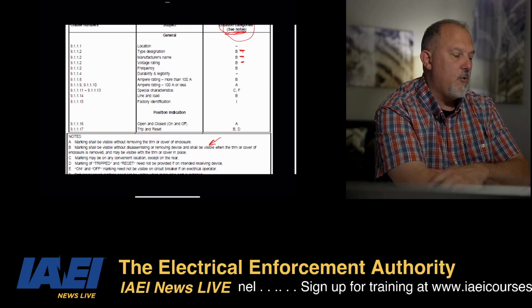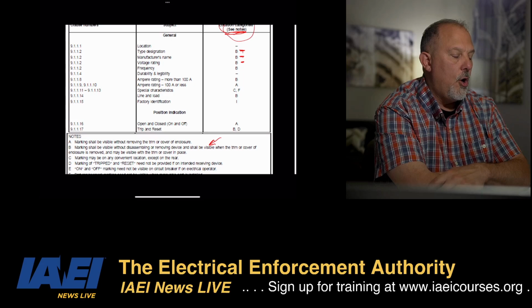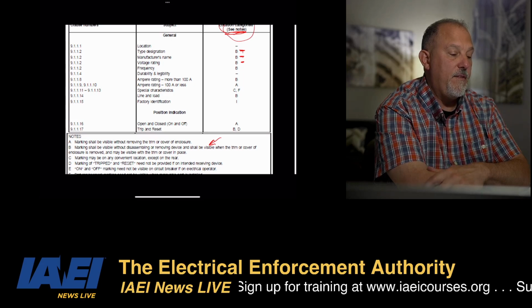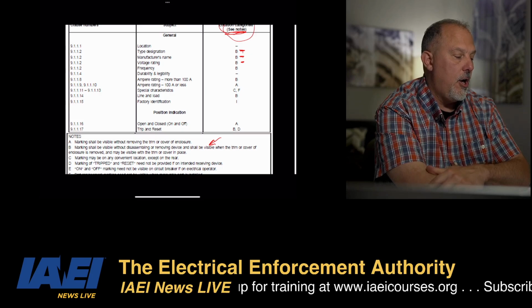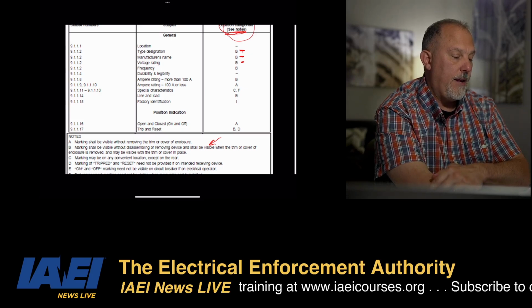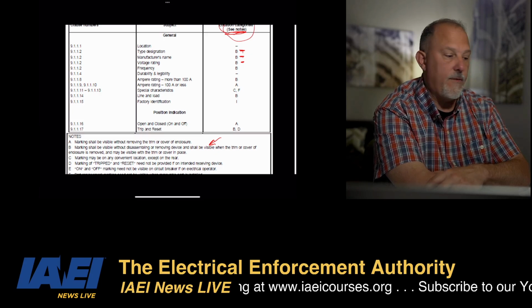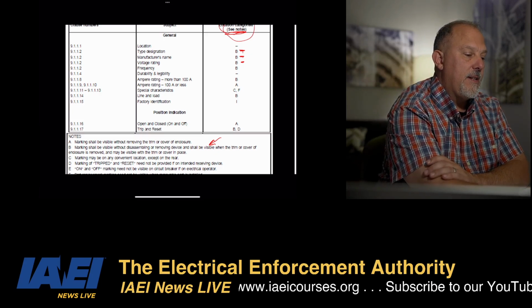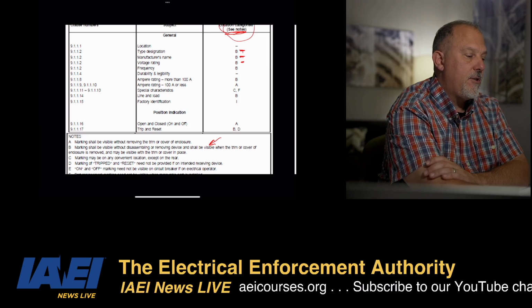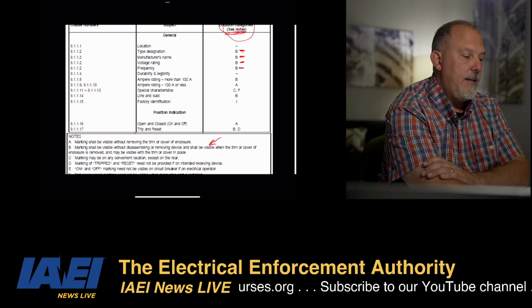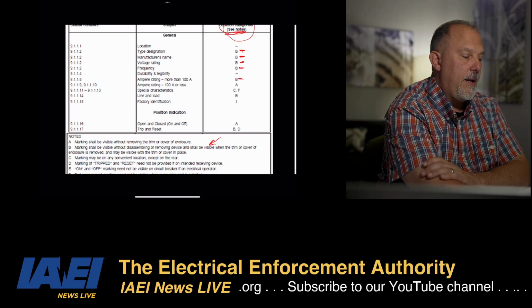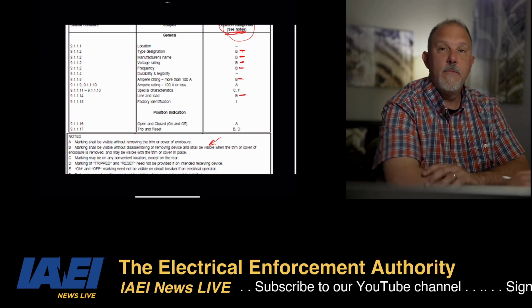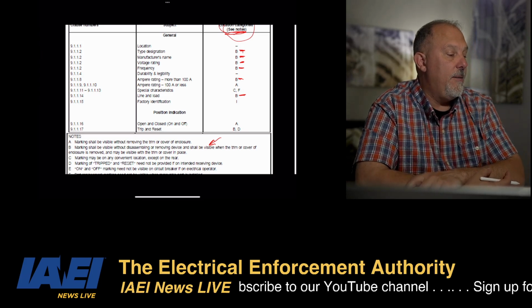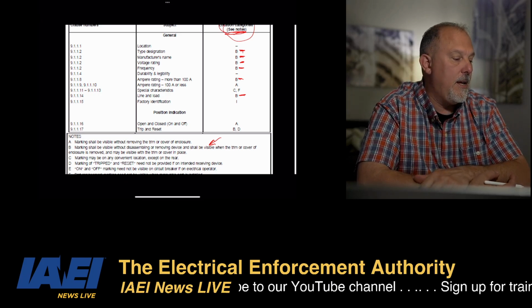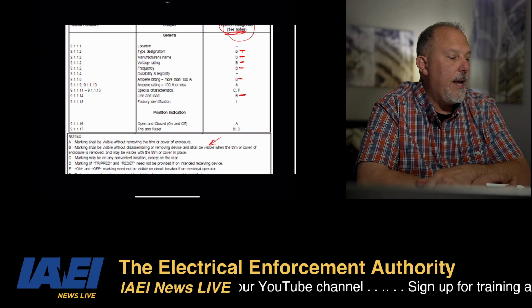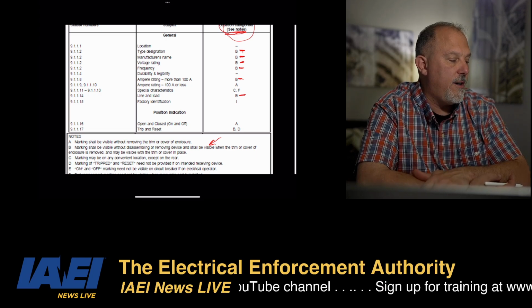Marking shall be visible without disassembling or removing the device, and shall be visible when the trim or cover or enclosure is removed and may be visible with the trim or cover in place. So you have to have the type designation, the manufacturer's name, the voltage rating, the frequency, and the ampere rating, and the line and load. Those are the ones that have to be visible without disassembling or removing the device, and be visible when the trim or cover of the enclosure is removed.